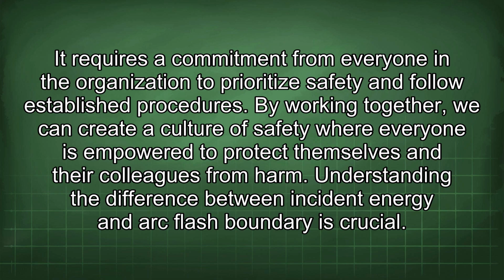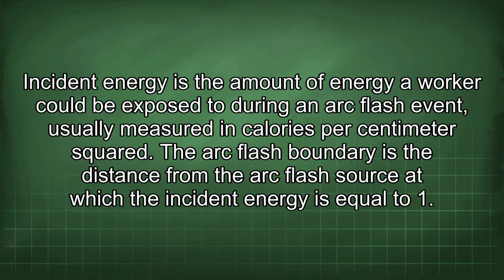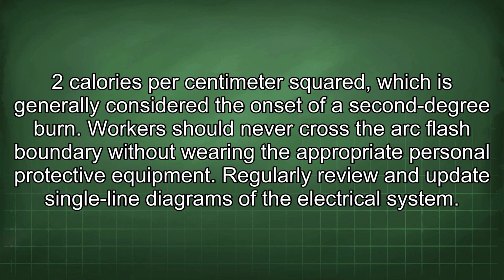Understanding the difference between incident energy and arc flash boundary is crucial. Incident energy is the amount of energy a worker could be exposed to during an arc flash event, usually measured in calories per centimeter squared. The arc flash boundary is the distance from the arc flash source at which the incident energy is equal to 1.2 calories per centimeter squared, which is generally considered the onset of a second-degree burn. Workers should never cross the arc flash boundary without wearing the appropriate personal protective equipment.